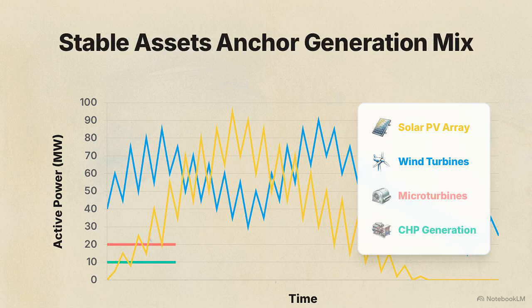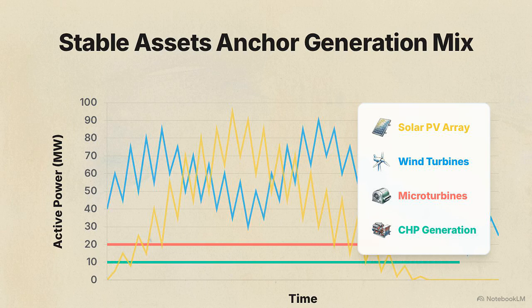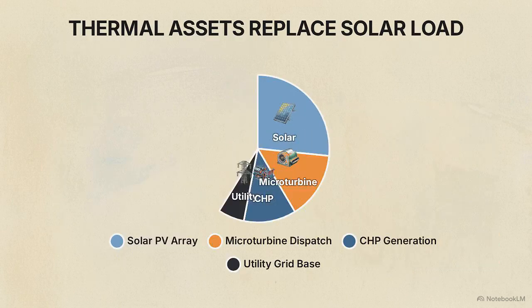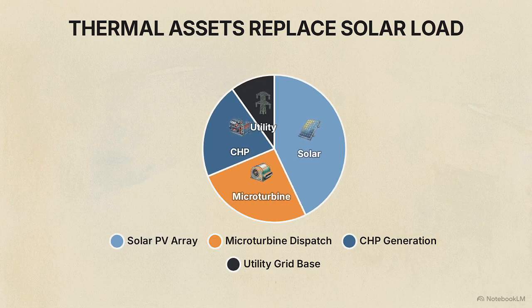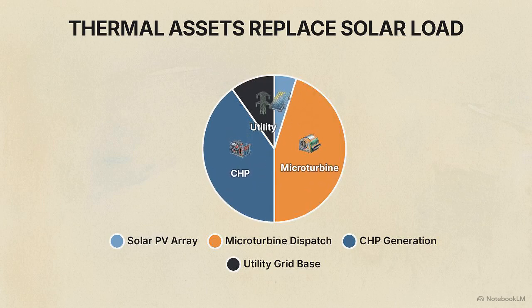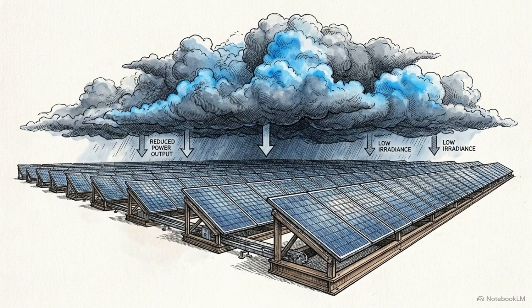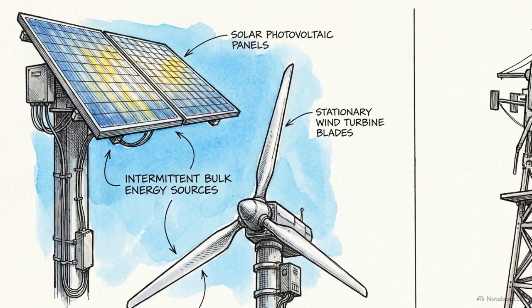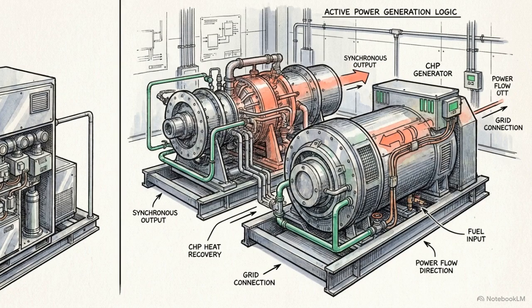A functional grid dictates that this intermittent power must be anchored by controllable thermal and mechanical assets. We introduce the steady output of synchronous microturbines and combined heat and power generators. These map as smooth, predictable curves. Through dynamic load sharing, the CHP units and microturbines are actively dispatched to cover the baseload, the exact moment the PV arrays drop out due to weather. Grid stability relies on a strict division of labor. Intermittent sources provide the raw bulk energy, while the mechanical sources provide the precise active power matching required to prevent total system collapse.